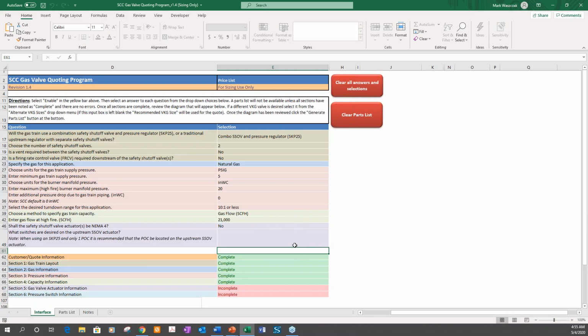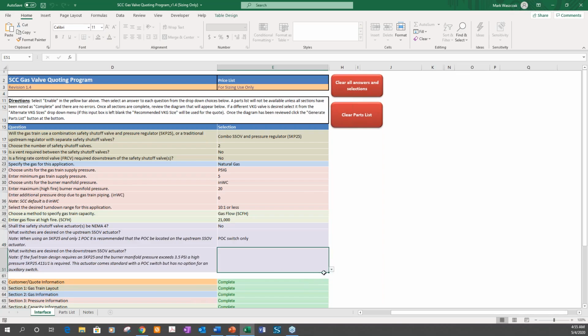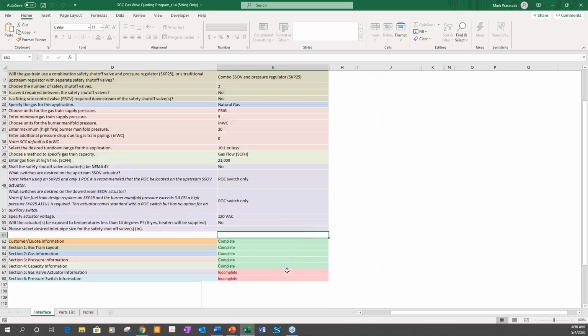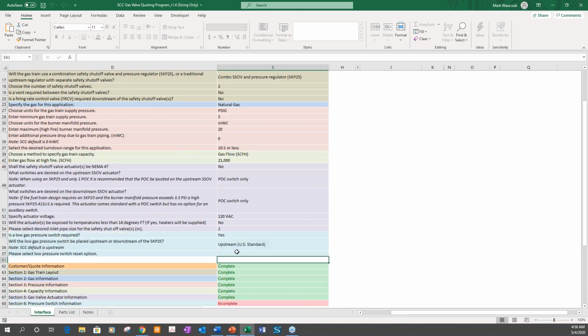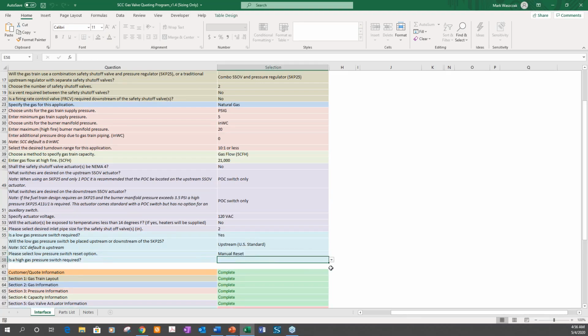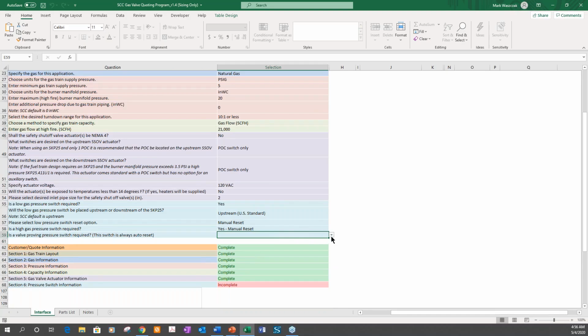What switches are desired on the upstream safety shutoff valve or actuator? We'll do the POC. And what switches are desired on the downstream safety shutoff actuator? We'll do POC as well. Next, select the desired inlet pipe size to the safety shutoff valve. We'll select 2-inch. Please select low pressure switch option. We'll do a manual reset. High gas pressure switch. We'll do manual reset. And then finally, is a valve proving switch required? And we're going to select yes.